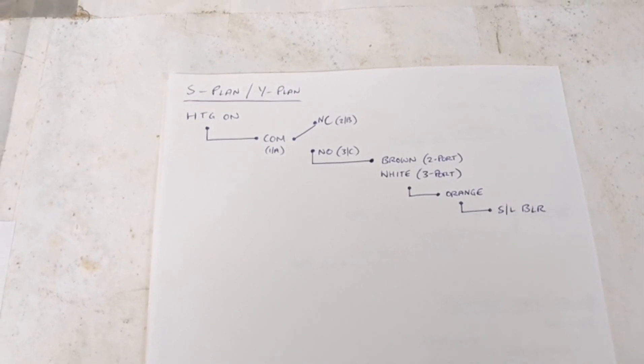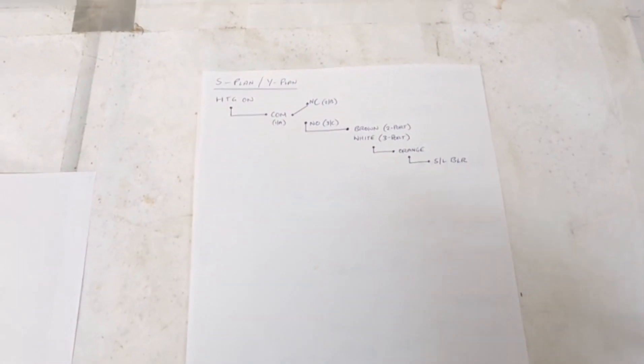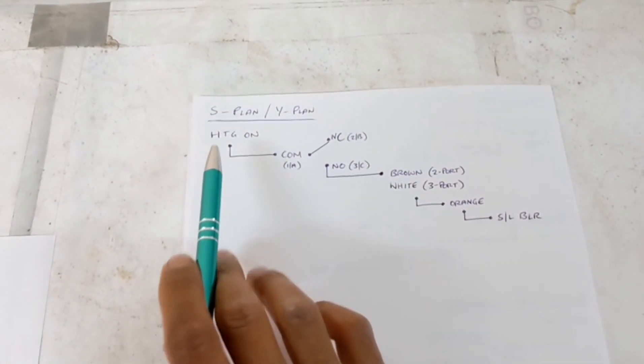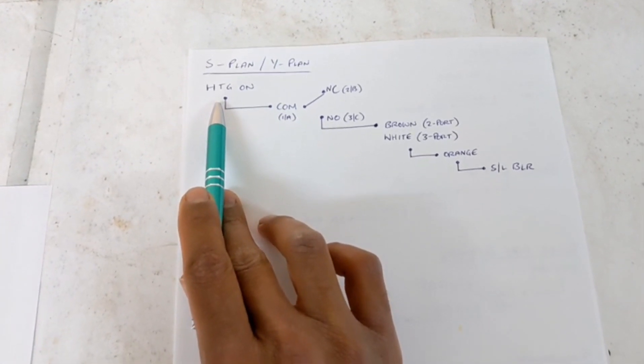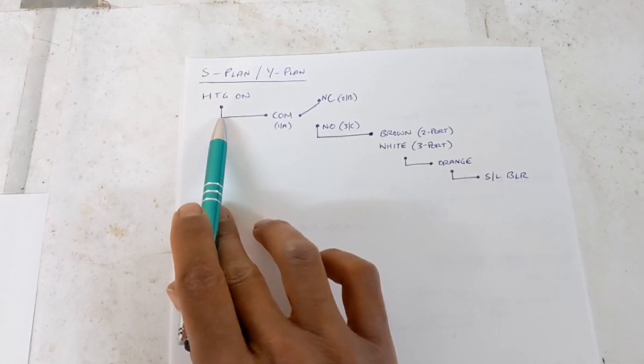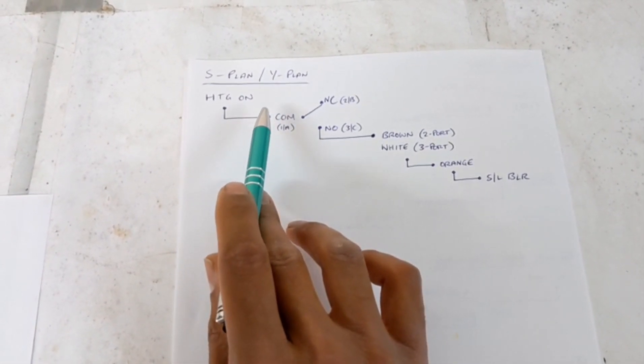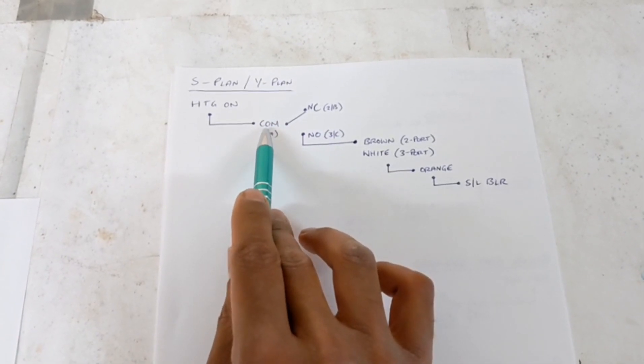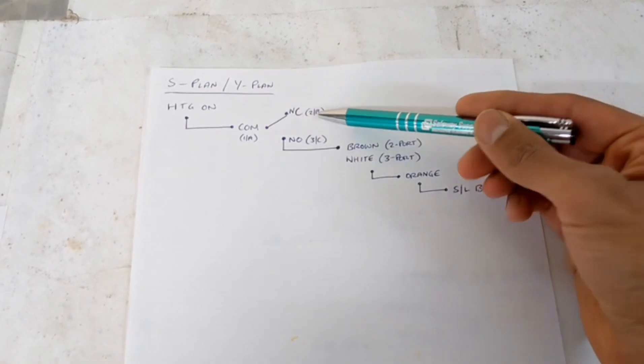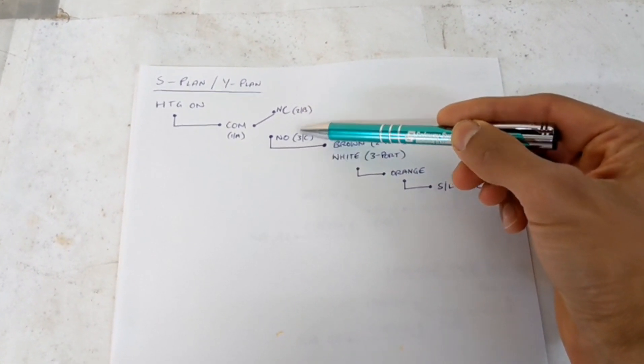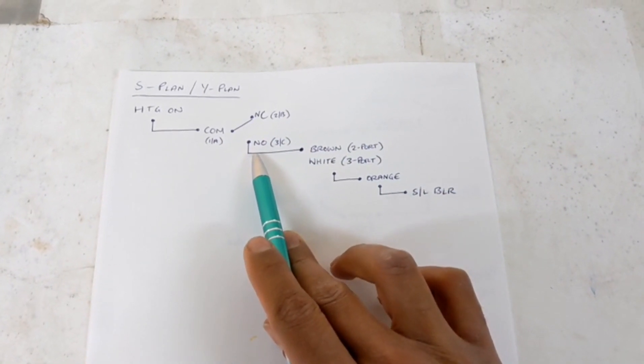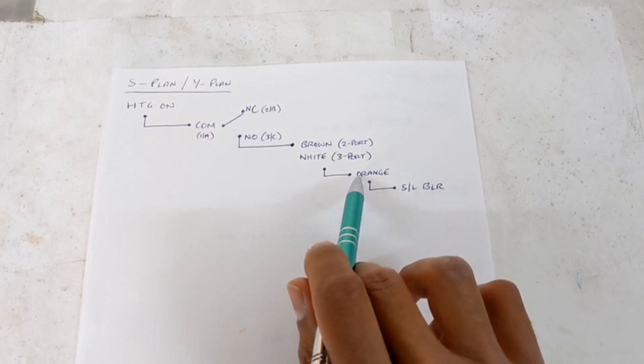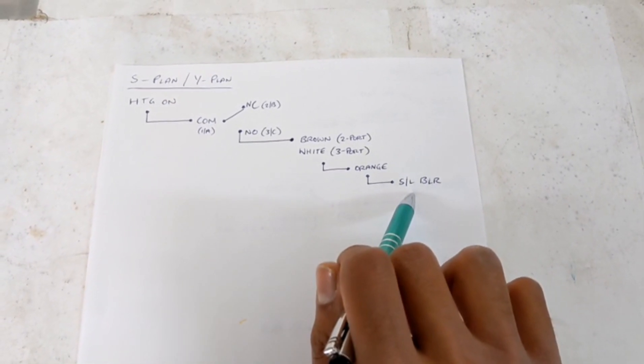The last one is how to wire up a room stat on an S-plan or Y-plan. You don't need to worry about the two ports, three ports, different cables, colored wires, or the programmer for this — just focus on the room stat itself. Regardless of whether it's S-plan or Y-plan, you're going to have a heating on signal from the programmer. That heating on goes straight to the common on your room stat — whether it's wireless or mechanical. At rest it sits at normally closed. When you turn the heating up it goes to normally open, and instead of going straight to the boiler it now goes to the brown wire on a two-port or the white wire on a three-port, which livens up the orange wire, which in turn goes to the switch live on the boiler to fire it up.